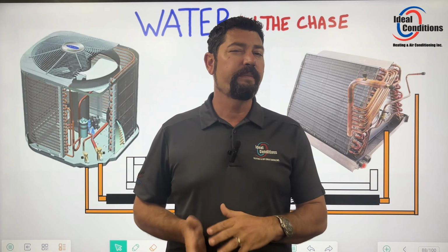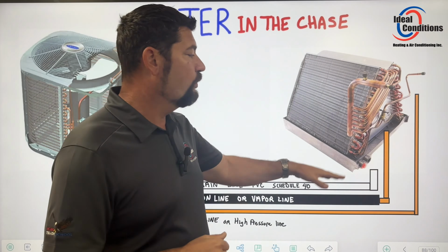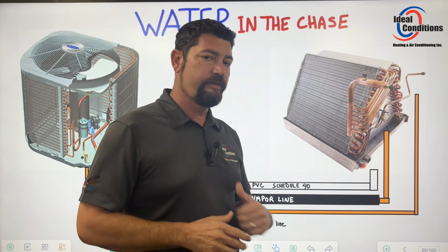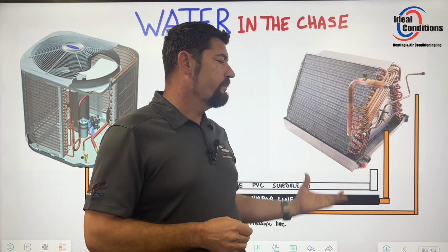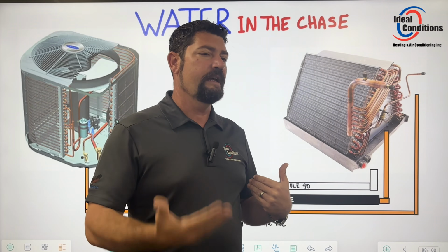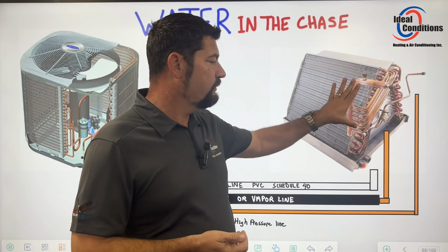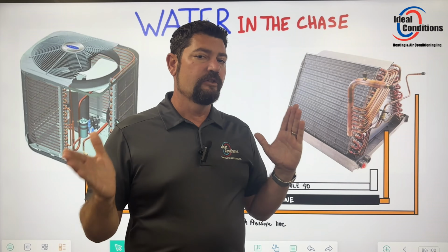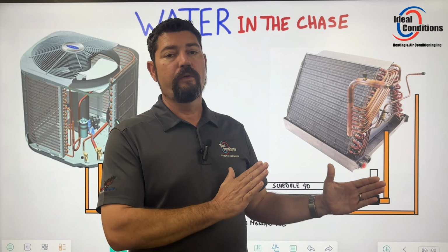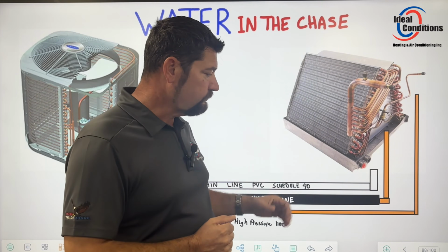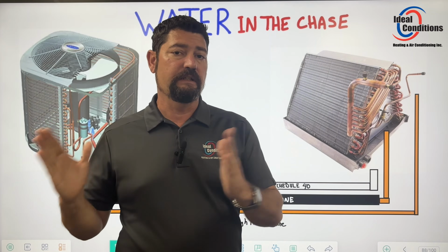The only thing that can drop it at that point is maybe the indoor temperature. If somebody cranked that thermostat down real low, in combination with an air filter that has more dirt built up on it, losing a little bit of CFMs, not boiling off as much, I should still be within 12 to 18, maybe closer to that 12 range. However, you shouldn't be drastically changing.